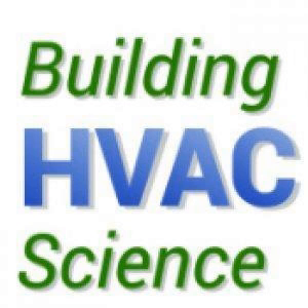So they're 200 amp CTs, and we can do single split phase, so you get 200 amp CTs, or 3-phase. In those packages, you're going to get 3 200 amp CTs. So we can actually manage up to 600 amps coming into a building. And if you have more of a custom solution for a larger building, that's where we kind of step aside and say, let's hand that to eGauge, who's got a great product, but even Johnson Controls and Siemens.